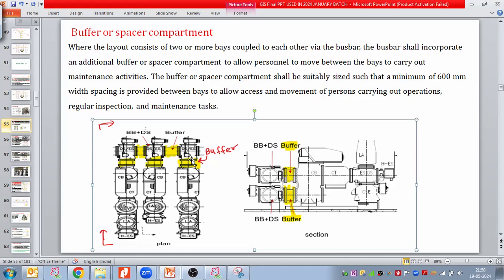And this is also important when we are doing degassing. Here we have taken a buffer at two locations: one in the common bus bar, plus a buffer between the disconnectors and the breaker module as well. Here we have the breaker module and here we have the disconnector module. So for maintenance purposes, a buffer module is given between the disconnectors and the breaker.